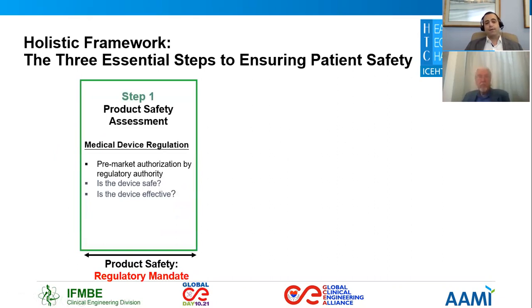At step 1 is the product safety assessment. The user must ensure that the marketed product has been cleared or certified by the relevant regulatory authority of whatever district or jurisdiction the product is being marketed in. This is to ensure general product safety and compliance with the regulatory requirements of a medical device regulator.